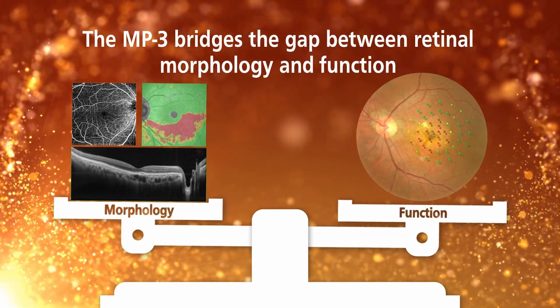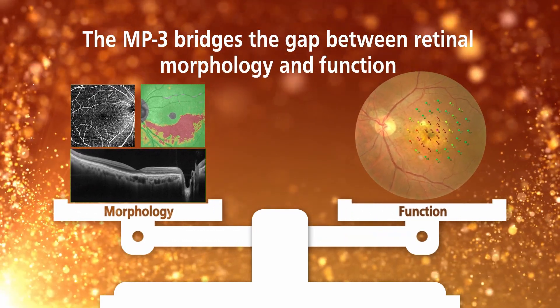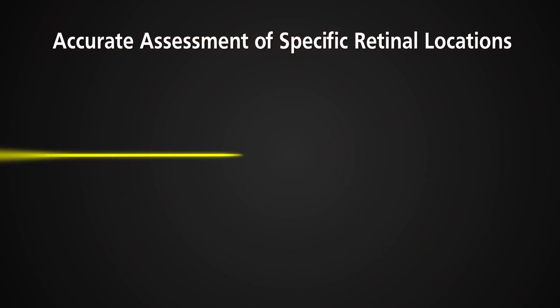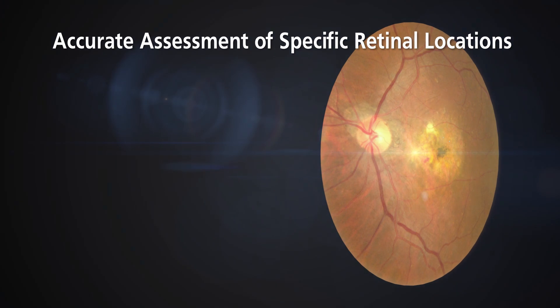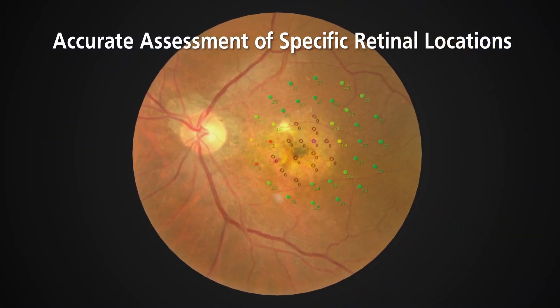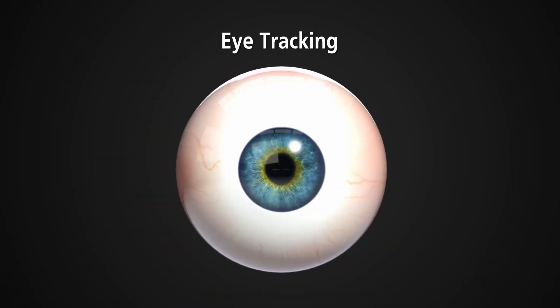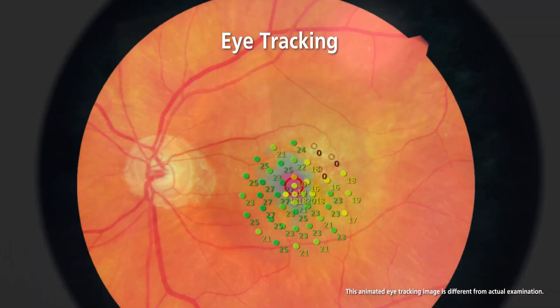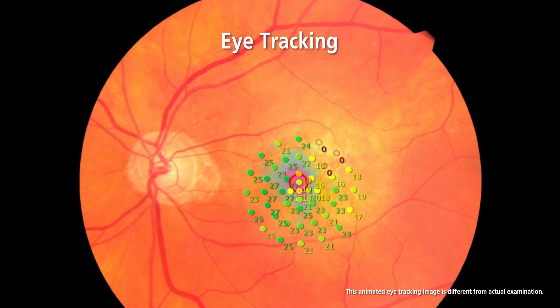The MP3 bridges the gap between retinal morphology and function. This microperimeter provides an accurate assessment of retinal function by testing retinal sensitivity at specific retinal locations that can be selected based on the area of treatment. A very fast 30Hz 3D eye tracker ensures precise placement of stimuli to the region of interest.